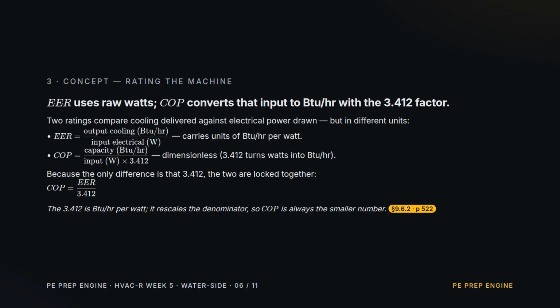Concept: rating the machine. 2 ratings compare the cooling delivered against the electrical power drawn, and they differ only in units. EER divides cooling in BTU per hour by the raw watts drawn, so it carries units of BTU per hour per watt. COP divides the same capacity by watts times 3.412, which converts those watts into BTU per hour. So COP comes out dimensionless. Because that factor is the only difference, COP equals EER over 3.412, and it is always the smaller number.